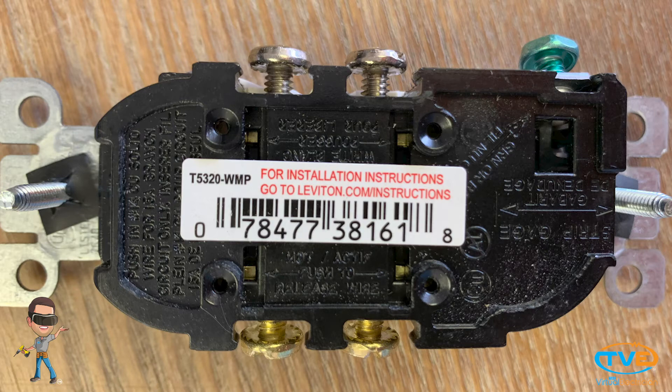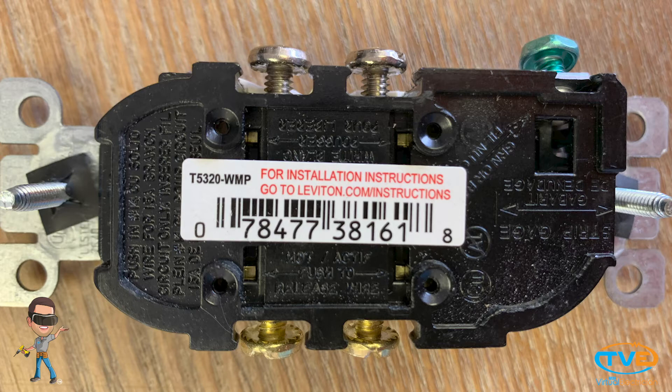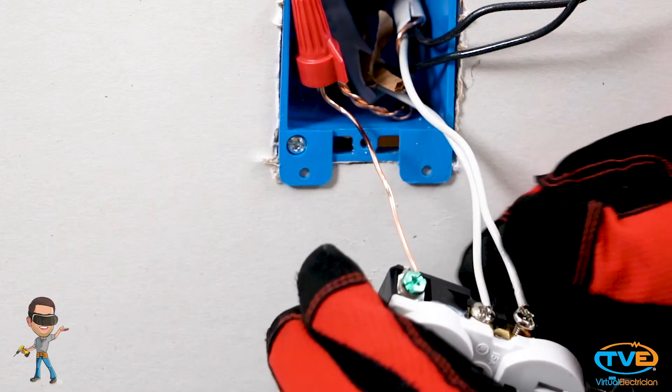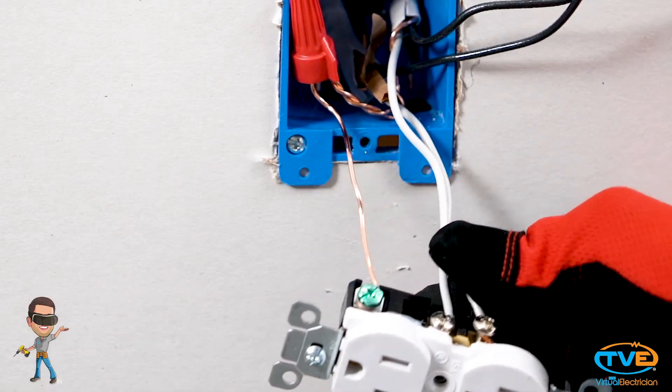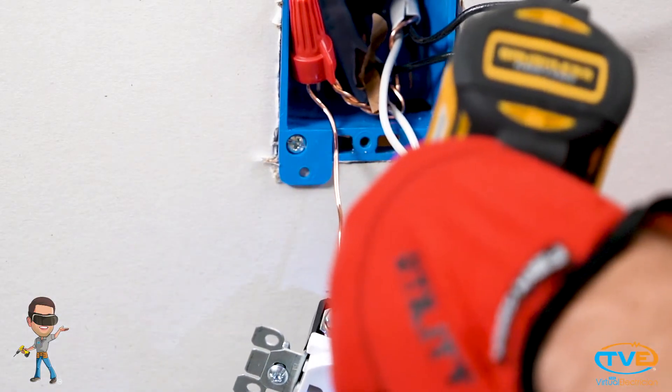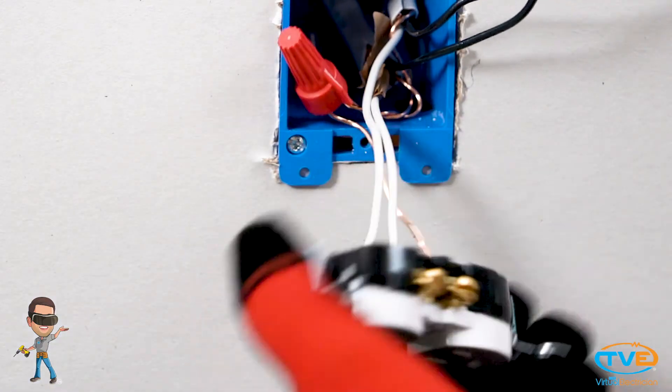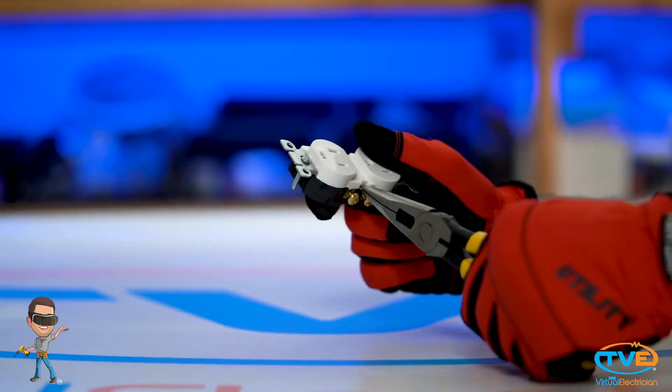And just like switches, there are these holes you can push the wires into if you choose to. Choose not to, please. Over time, these wires can loosen up and it could become a fire hazard. Make sure you make your loop and wrap it around the screw. It doesn't matter which wire goes on which screw because the two screws are linked together by this tab in the middle anyways.